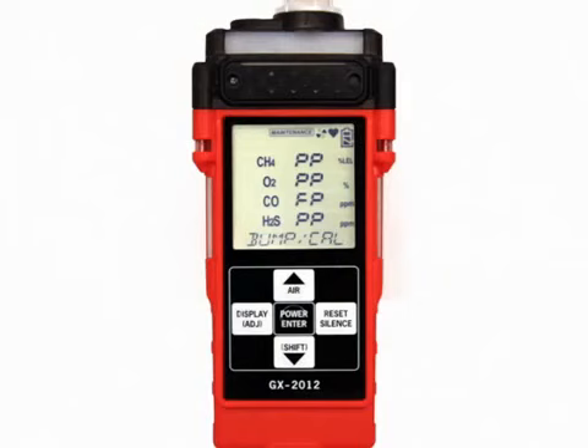At the end of the calibration, the instrument displays the results from both the bump test and the calibration. Use the Air or Shift buttons to scroll between the calibration bump test results, the bump test gas readings, and the calibration gas readings. To return to the bump screen in calibration mode, press power enter at any time.